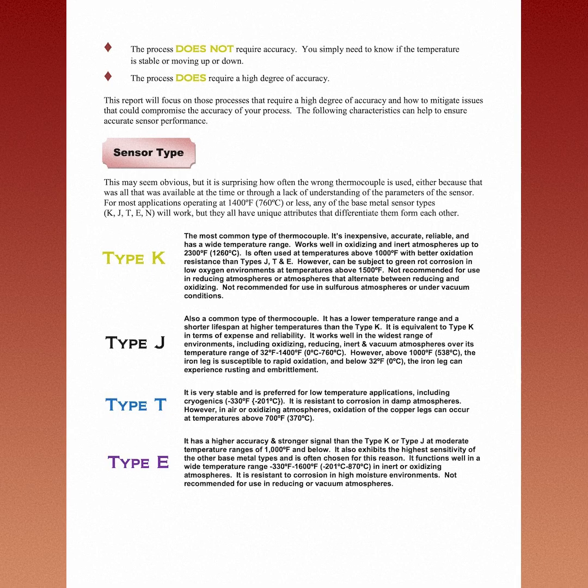Type T, very stable and preferred for low-temperature applications, including cryogenics, down to minus 330 degrees Fahrenheit or minus 201 degrees Celsius. It is resistant to corrosion in damp atmospheres. However, in air or oxidizing atmospheres, oxidation of the copper legs can occur at temperatures above 700 degrees Fahrenheit or 370 degrees Celsius.